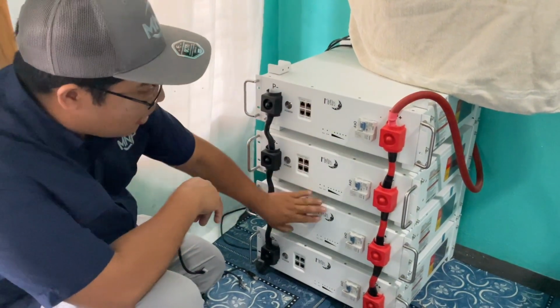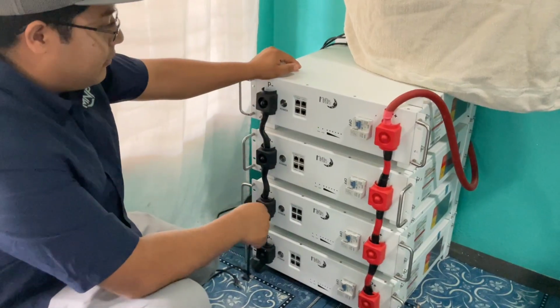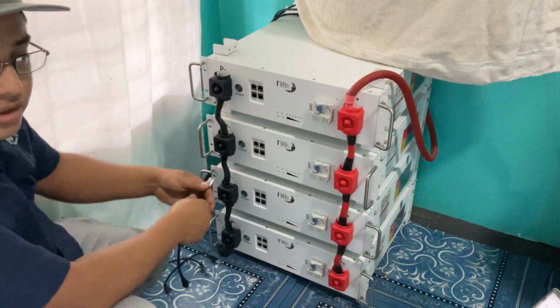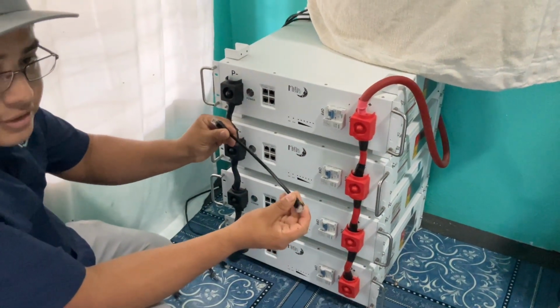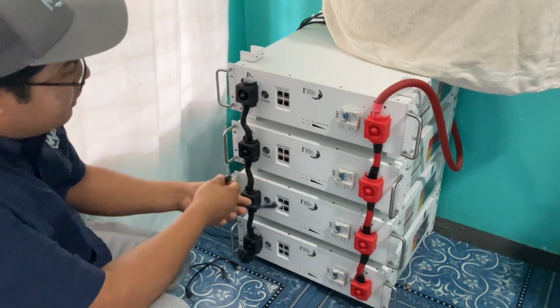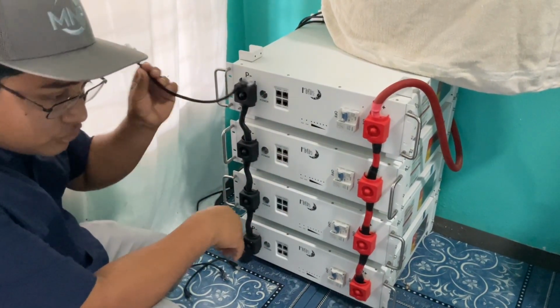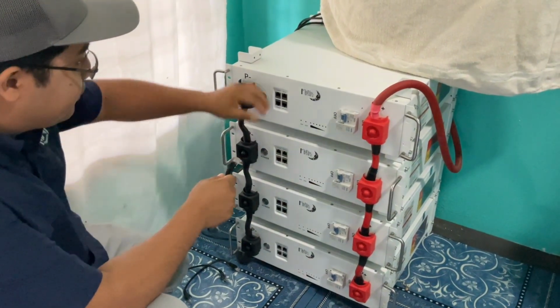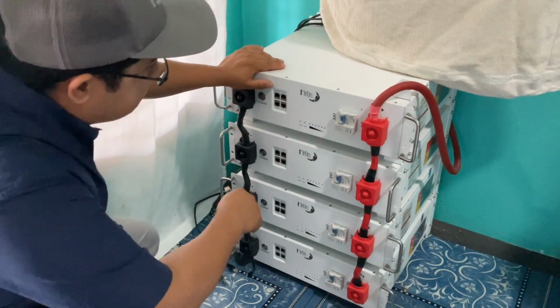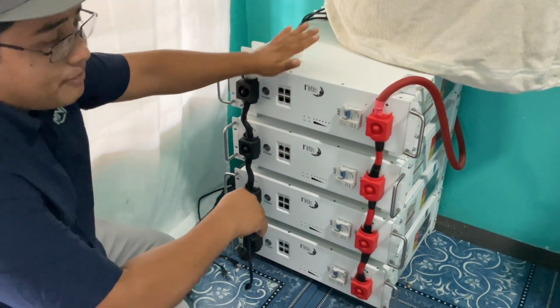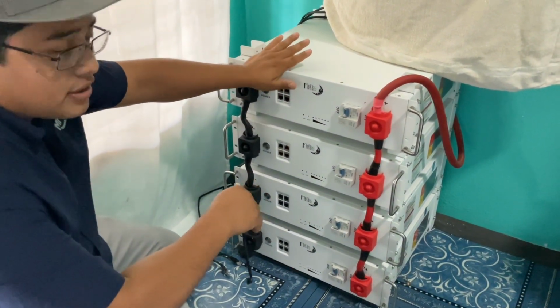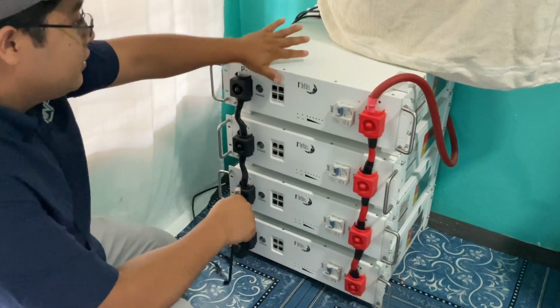Once all the lights and batteries are off, we're going to use the short cables that come with the batteries to link from battery to battery. Don't use any other cable, only the ones provided from the factory. In this case, the top battery will be our master battery, the one that communicates with the inverter.